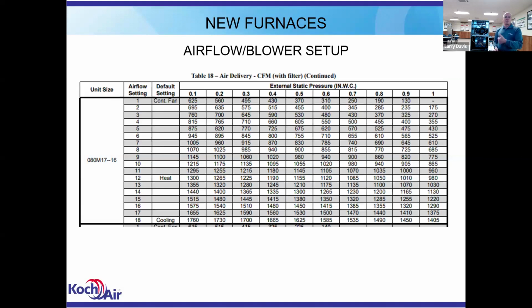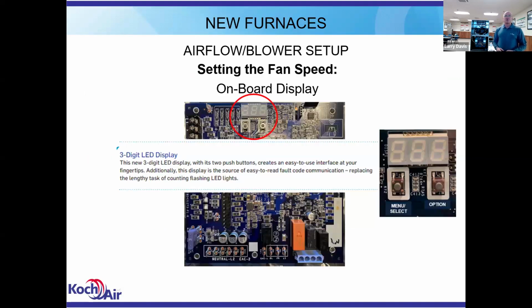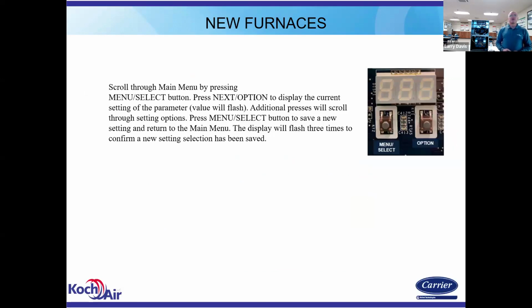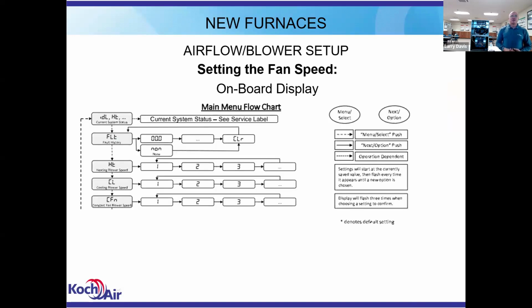Set your heat airflow with temperature rise, your cooling airflow with your external static pressure. So we determine what we want. We can do it a couple of different ways. We can use the buttons on the board and scroll through and set each one. You're going to use these, there's a better picture of it, reading the LCD display and the menu select button. You're just going to go through this menu. You'll scroll down to your heat blower fan speed, press the next button, and then select the speed that you want. Press it again to save it.